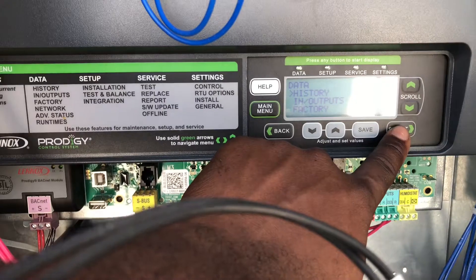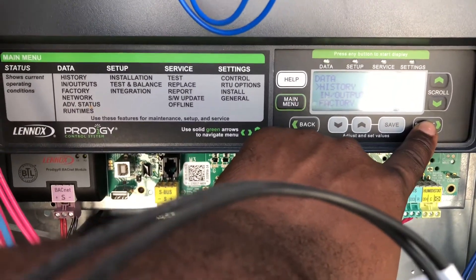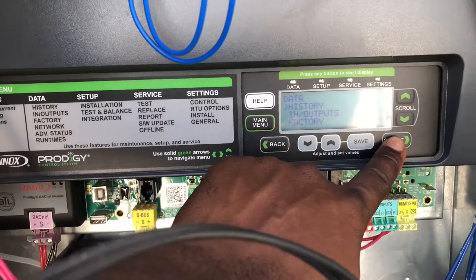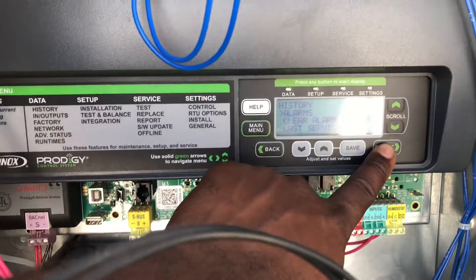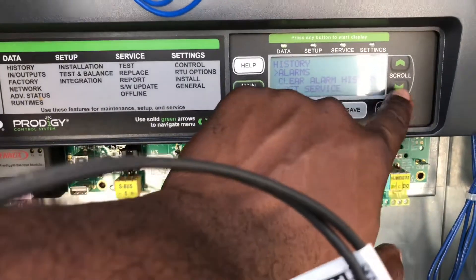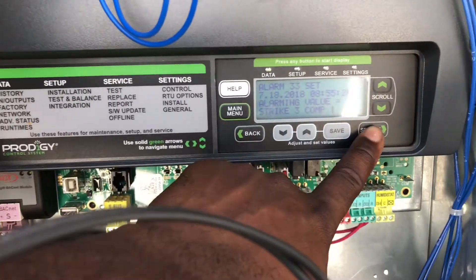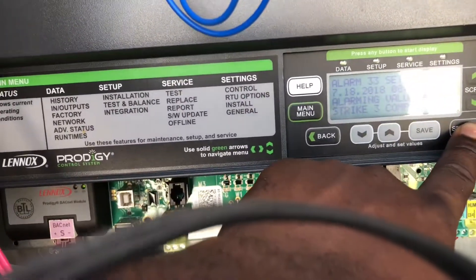If you want to find out anything about these units, it's all here. Right now I want to look at the history because I want to see if there have been any alarms, so we're just going to hit select. There you have your alarms, clear alarm history, and last service. I want to look for the alarm, so I'll hit select again. 7/18 — today's the 18th — so at 8:55 a.m.